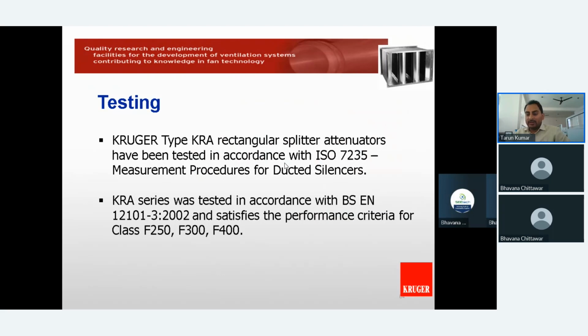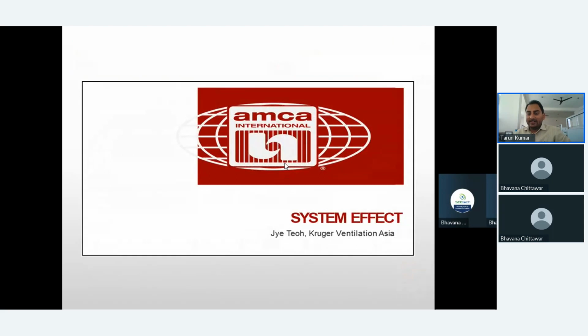So we will go for the 5-minute quick query. After that, I will also try to brief about the system effect. Rather than just selecting the fan, it is very important to know the system effect, what the system effect is in the ventilation segment, to deliver the proper air and to get better energy saving by taking the system effect into consideration. So in the fan segment, if you have any query, we can proceed with the queries first.